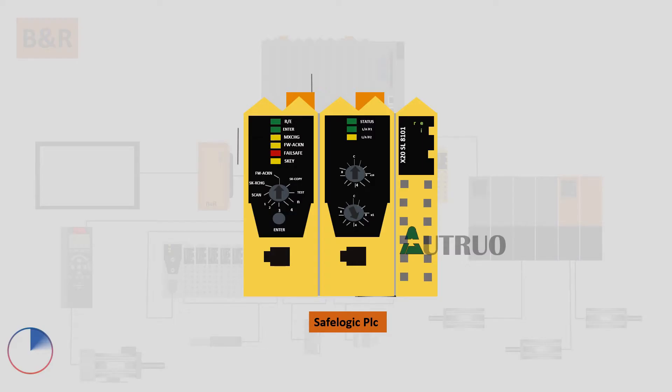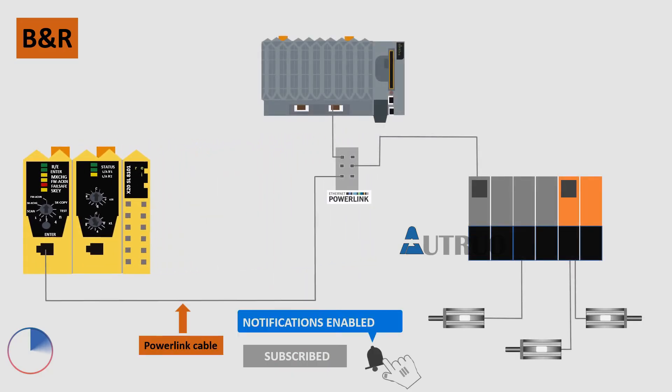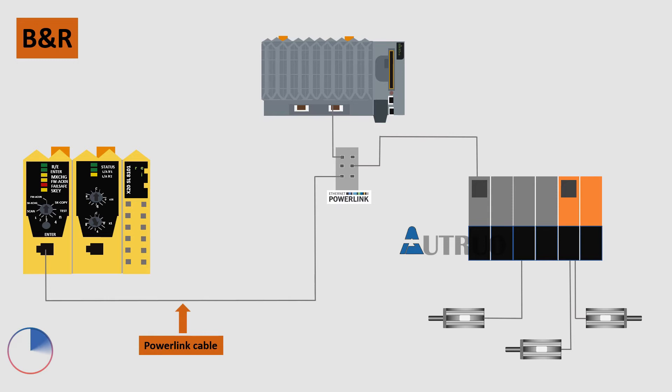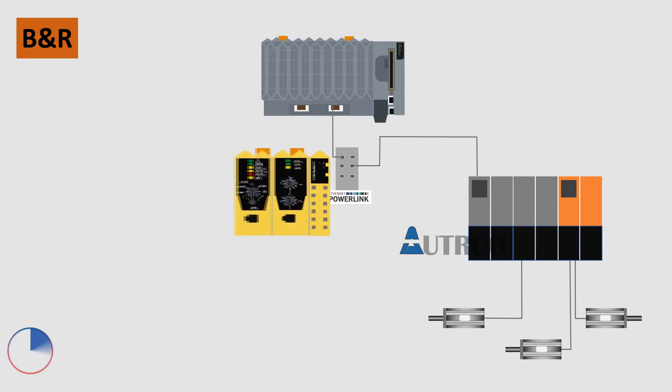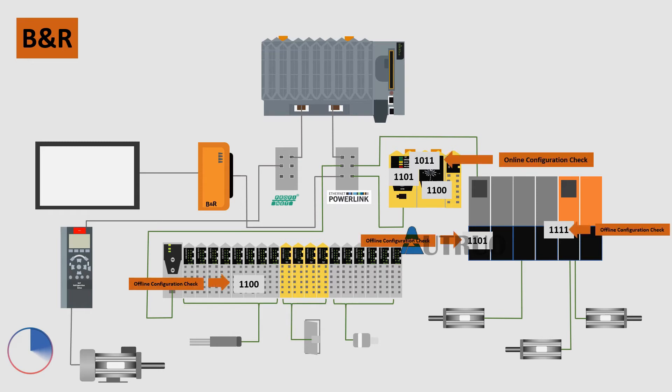The Safe Logic PLC is a stand-alone PLC within the B&R system. This PLC is usually connected to the X20 CPU through the use of the PowerLink communication protocol. The PLC monitors all the safety components on the B&R system and checks the safety configuration of all B&R components during startup — that is, the field configurations will be compared with the Safe Logic's stored configurations.